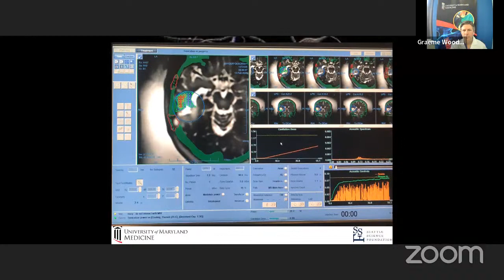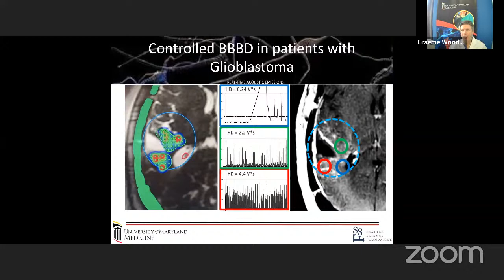So this is what this can look like in the post-treatment scan. And so in the early days, we saw a relatively non-uniform deposition of energy, in part because of differences in blood vessel density within these regions, and also just differences in the tissue characteristics. So the system was not able at the beginning to achieve a relatively uniform mechanical dose throughout the target region. And so we were able at that time to look at differences in harmonic dose within the target regions and gauge the degree of contrast enhancement. For example, here, a low amount of harmonic dose corresponded with a relatively little amount of new contrast enhancement following the treatment. A moderate harmonic dose corresponded to a moderate amount of new contrast enhancement, and a relatively high harmonic dose corresponded with a higher amount of new contrast enhancement, beginning to create this ability to envision a sort of dose response to a desired bioeffect, in this case, new blood-brain barrier disruption.